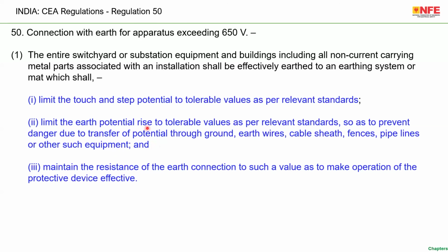Limit the earth potential rise to tolerable values as per the relevant standard so as to prevent danger due to transfer of potential is the second requirement of the regulation. The third requirement of the regulation is maintain the resistance of the earth connection to such a value as to make operation of the protective device effective. You see, effective is very important. That means whatever the value you are getting should be stable. You set the relay on a stable value, meaning the earth system, including the connections, the values of the RE or other return path should not change based on the climatic conditions.